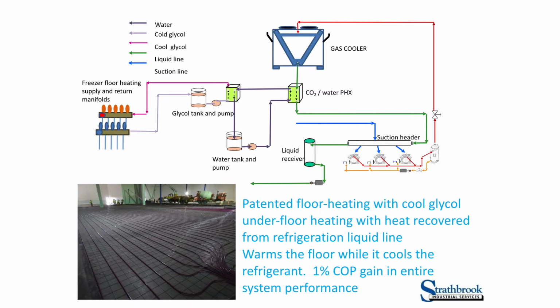The other thing we did was we took out a patent on a floor heating system. So we've got the same basic starting point under the floor, but instead of heating the glycol with the heat from the discharge, we're now taking heat from the liquid line. So if I take the refrigerant to take all the heat I can out of it in the condenser, whatever temperature I get now is what I'm stuck with. And there are losses in that the colder it is, the more energy efficient the plant will be. So we started to scavenge heat out of the liquid line to heat the floor.